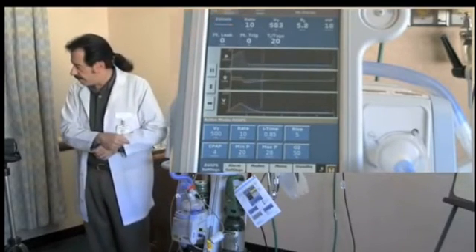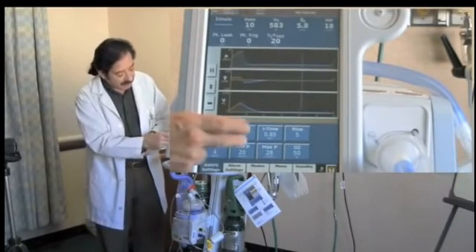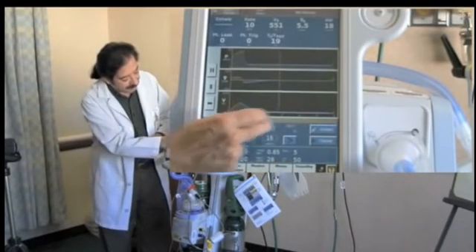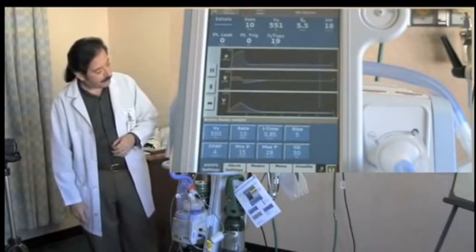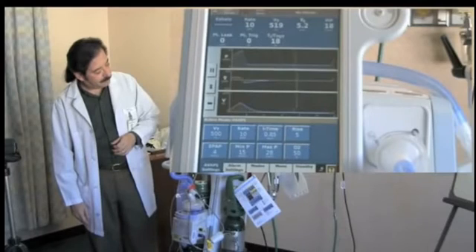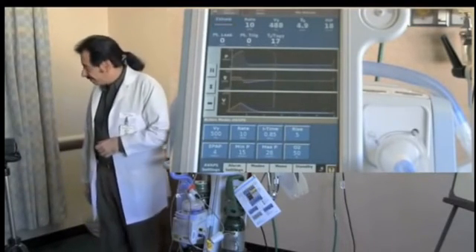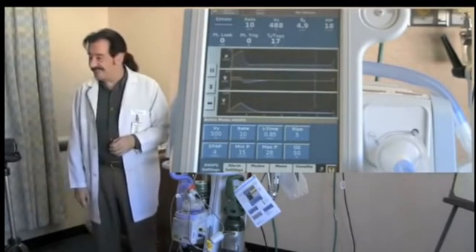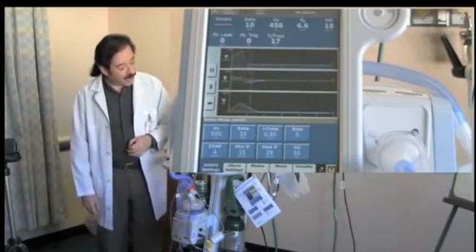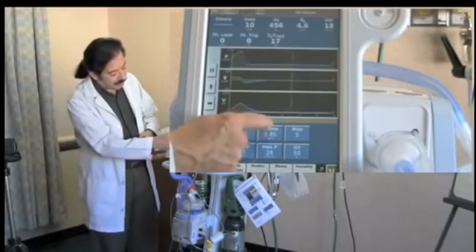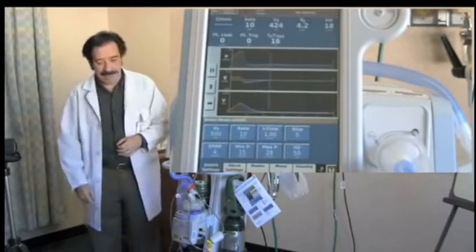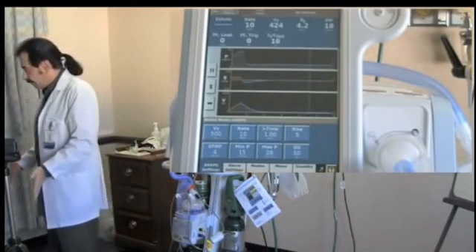Okay, so now I started dropping it there, but not fast enough, so now I can take my P min and let's drop that down to 15 and see what happens. Okay, well, like anything in PRVC, it's never quite perfect, is it? Okay, so I dropped a little bit too high. What I'm going to do in this case is just bump up my I-time to 1 second, and that should get me about as close as I'm going to get to 500.